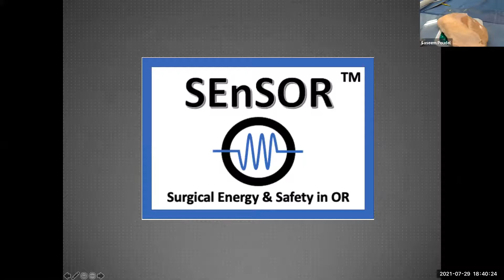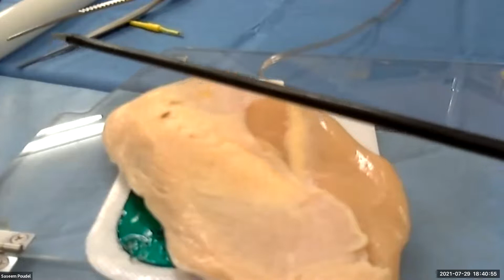So here I have one instrument. This has an insulation failure. Look what happens: if I activate it, it's not supposed to burn here, but because there is failure, it will burn here. But what happens is our eyes are generally on the tip, and you never know if it was touching bowel, and then you may have a bowel leakage afterwards. You check the videos again and again and don't know how the bowel leakage happened. But if you have insulation failure, smaller breaks can actually cause larger damage.